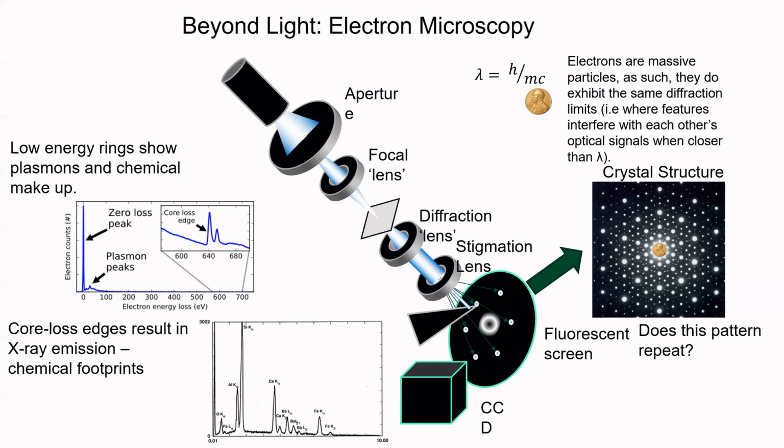So you start off with an electron gun of some sort. Usually these days they're field emission guns. Well, you have to have some way of extracting the electrons from the source and accelerating them out very fast. You then have to have some kind of focusing. In an electron microscope, we primarily use electromagnetic lenses to do that focusing. You then end up going through your sample. You then have more lenses at the back of it.